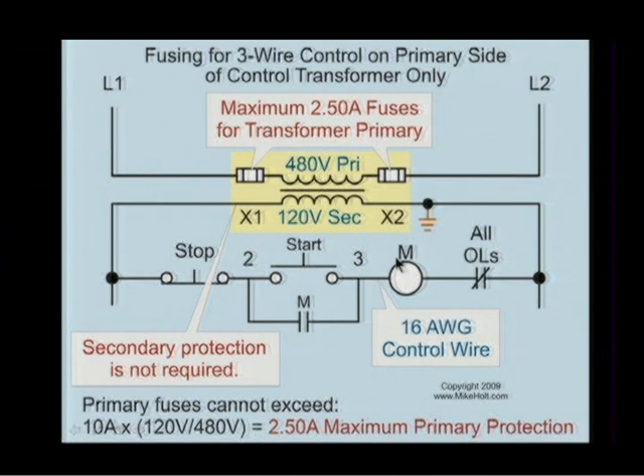And that is this. Your primary overcurrent protection can be used to provide overcurrent protection for the secondary, as long as it's a 2-wire primary and a 2-wire secondary. Actually, as long as it's a 2-wire secondary is the only critical thing, without getting into the details as to why. 2-wire primary and a 2-wire secondary. And you can get into the code book, and it has to do with a ratio and how this is going to work out, which I think is beyond the scope right now, unless you guys think we should talk about that ratio. Okay, just simply that primary protection.